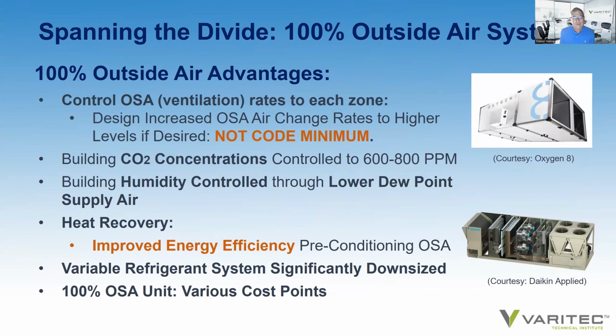So what are the outside air advantages? Well, you can control the outside air rate to each zone. That is to say, there's no question about outside air hopefully mixing at the appropriate ratios within the return air and is consequently uniformly distributed throughout a building. You can provide the outside air required for each zone directly into the zone. And consequently, you have deeper control of your outside air, and you're not necessarily limited to designing to code minimum as defined by ASHRAE 62.1. In fact, ASHRAE in its Epidemic Task Force guidelines recommends designing outside air volumes at rates greater than the minimum to reduce the risk of infection.